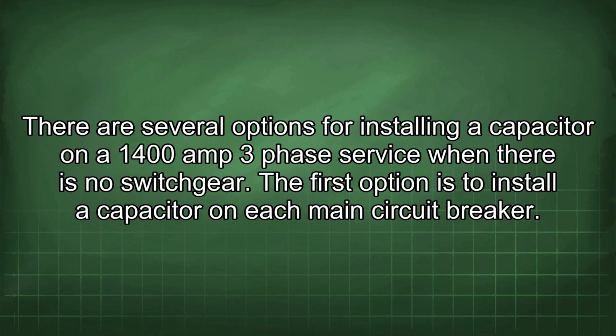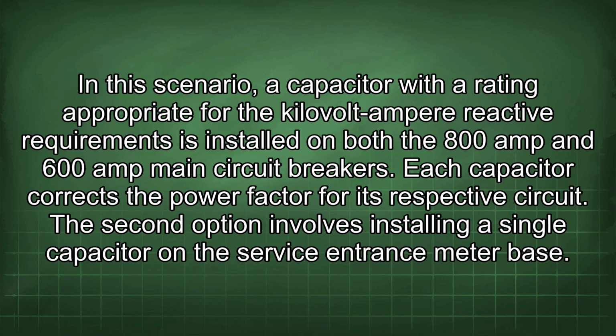There are several options for installing a capacitor on a 1400 amp 3-phase service when there is no switchgear. The first option is to install a capacitor on each main circuit breaker. In this scenario, a capacitor with a rating appropriate for the kilovolt ampere reactive requirements is installed on both the 800 amp and 600 amp main circuit breakers. Each capacitor corrects the power factor for its respective circuit.